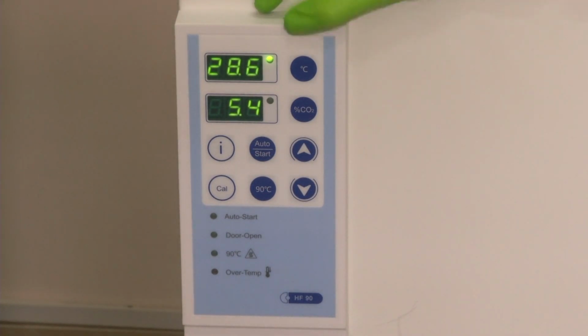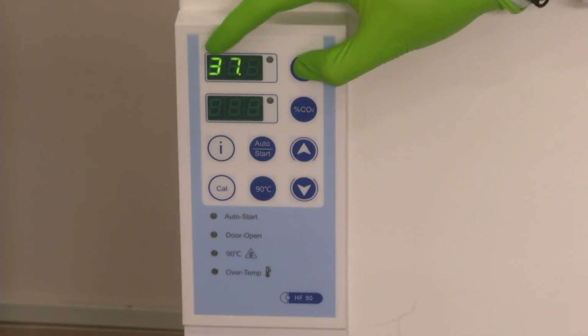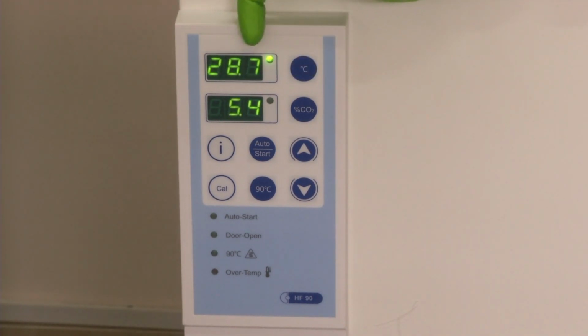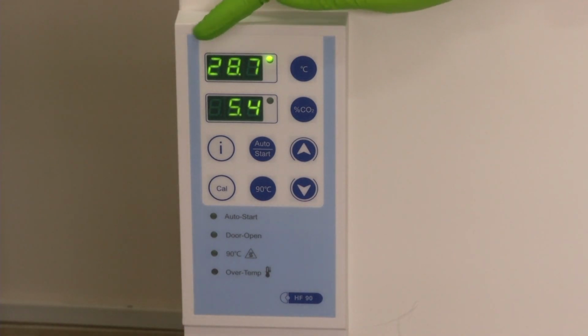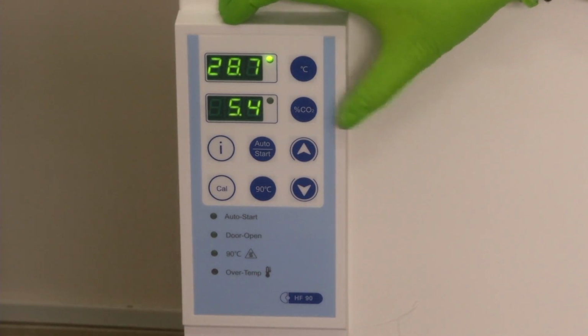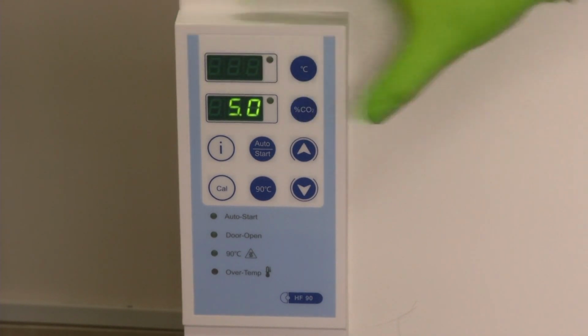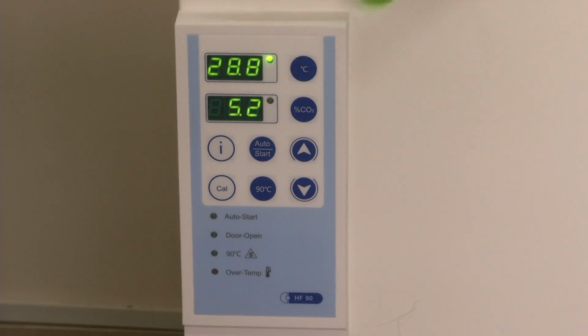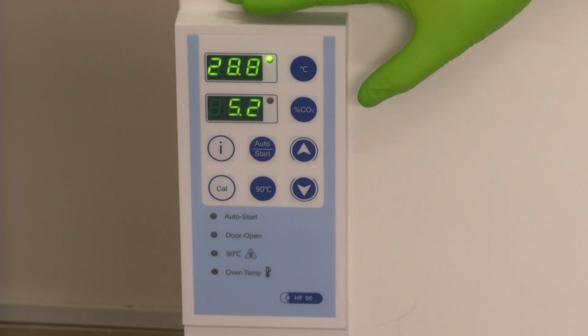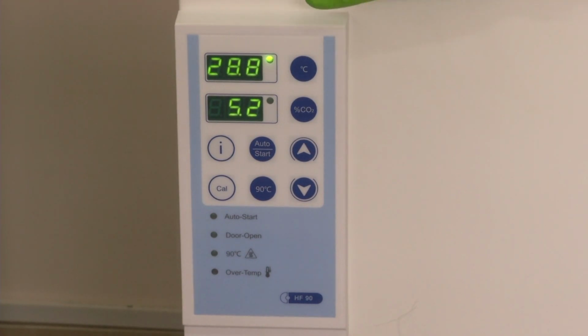So, let us press the degree Celsius button. If you press it, you will see that it is set to 37 degrees Celsius. See, it is very clearly visible. If you release it, it will show the current temperature that it is about to reach. It is slowly ramping up to 37 degrees Celsius. Likewise, if you press percentage CO2, you will see that it is set to 5% CO2. If you release it, right now you will see that around 5.2% CO2 is there, which is roughly equal to what we have set. Now, 95% relative humidity is maintained through another mechanism inside the incubator, which we will see shortly. So, these are the major controls in the incubator.